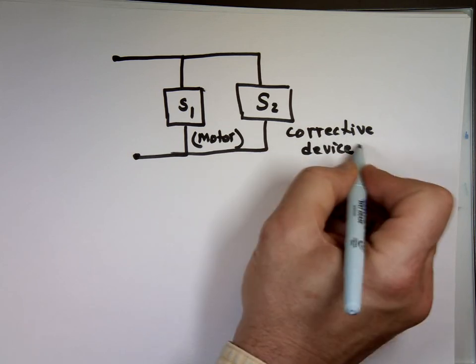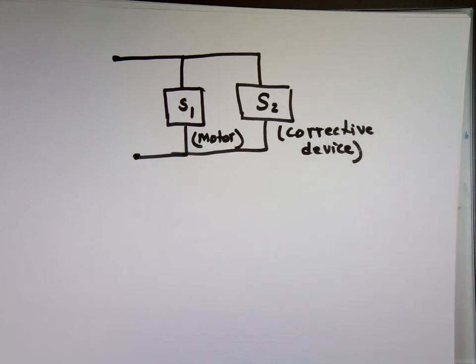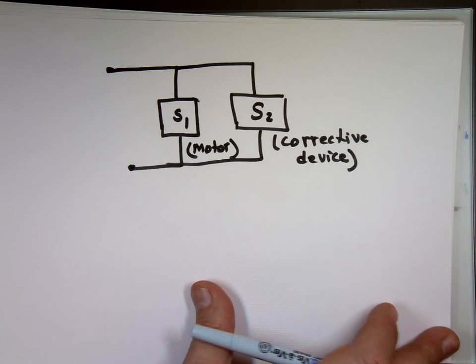The Basketball Hall of Fame had that issue. When they built it, somebody said to me, I forgot how many thousand feet of cable, thousands of miles, not even feet, of cables going through the Basketball Hall of Fame. So the power factor was not really good, so I had to bring in a big capacitor and put it in parallel with the load to bring that power factor to a better number.